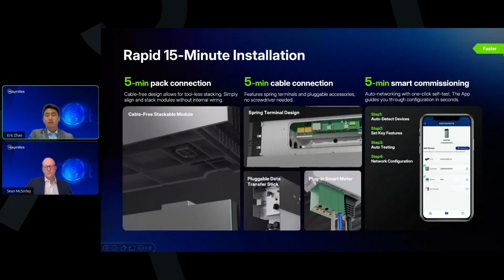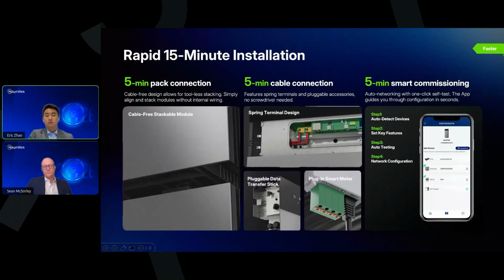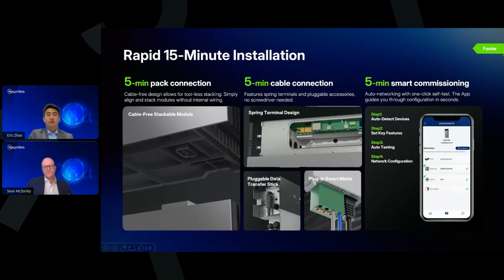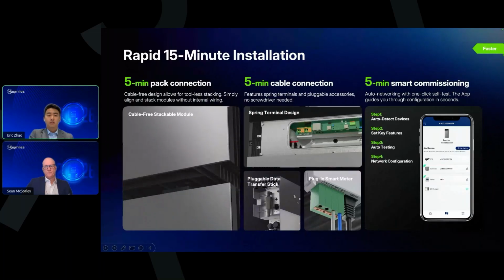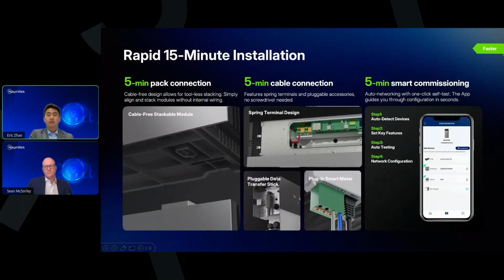For commissioning, the system supports automatic device detection, key feature configuration, automatic testing, and network configuration. For example, if the CT direction or phase sequence is incorrect during commissioning, the system can detect the issue and correct it automatically. This helps reduce configuration errors and saves troubleshooting time on site.